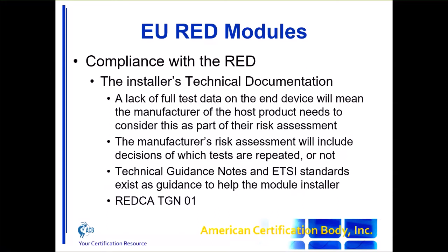A lack of full data or evidence to that latest standard obviously could mean a trip to a notified body, but any kind of acceptance of test data from a module manufacturer into the host product is obviously going to be a pretty big part of the manufacturer's risk assessment, and that's the installer's risk assessment. And there is pretty clear guidance on this called TGN01.